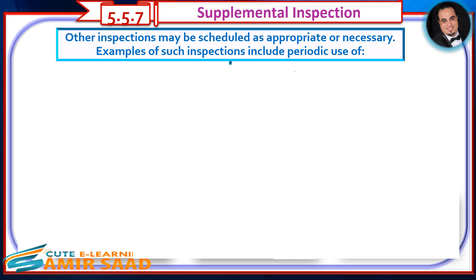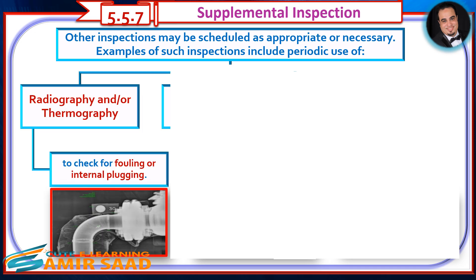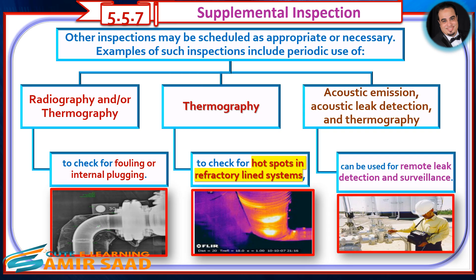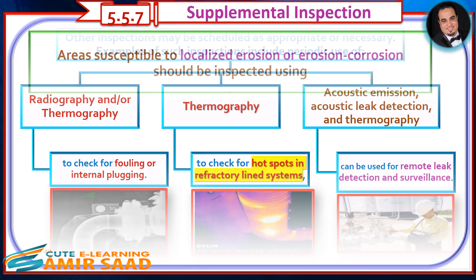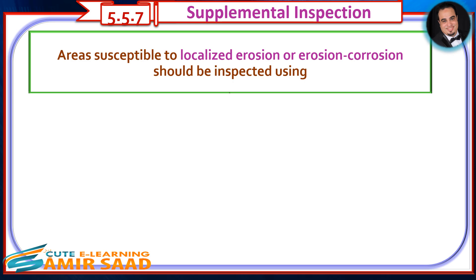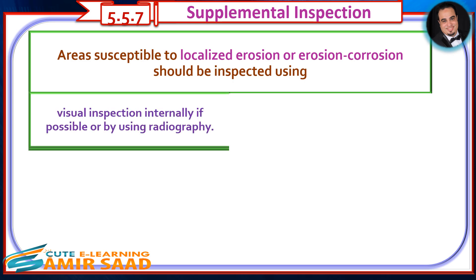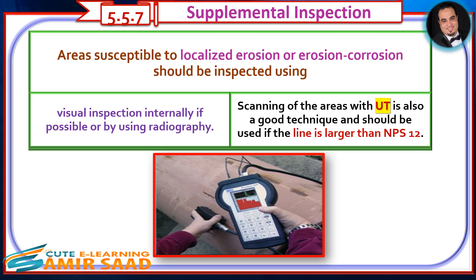Other supplemental inspections may be scheduled as appropriate or necessary. Examples include periodic use of radiography and/or thermography to check for fouling or internal plugging, thermography to check for hot spots in refractory-lined systems, and acoustic emission or acoustic leak detection for remote leak detection and surveillance. Areas susceptible to localized erosion or erosion-corrosion should be inspected using visual inspection internally if possible, or by radiography. Scanning with UT is also a good technique and should be used if the line is larger than NPS-12.